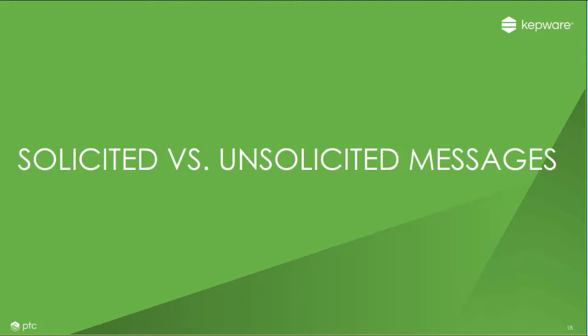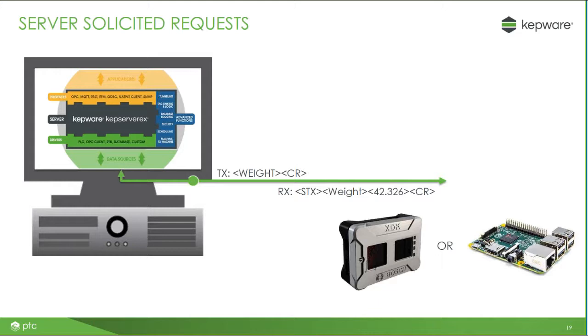Now let's look at the driver itself, starting with solicited versus unsolicited messaging. One traditional way to interact with a device is to solicit a message or request. KepServer builds a transmit message and sends it over the wire to a particular device, which then interprets the message and responds according to its protocol document. In the example shown, KepServer is sending a transmit message of 'weight' to the device. The device takes that weight command, responds with that same request message followed by the actual weight value. KepServer then takes that message, strips out the non-meaningful ASCII characters, and selects the actual data that pertains to a particular tag value.